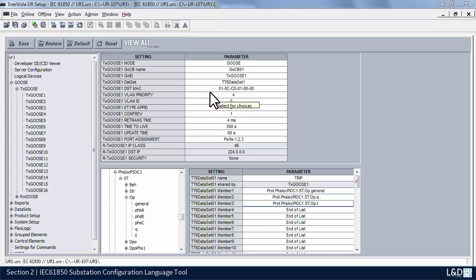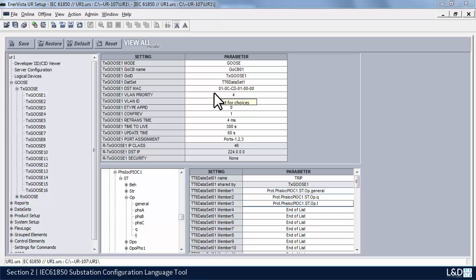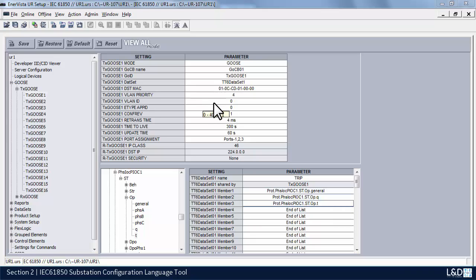The next field is the destination MAC. You can see this is the default as per the standard — it's optional, but the standard recommends using it. Always make sure the first octet has 01; if it's set to 00, then it's not multicast. The destination MAC is used by the network to restrict the delivery of messages. If we switch the GOOSE type over to a routable GOOSE, this field gets grayed out and we use a different field.